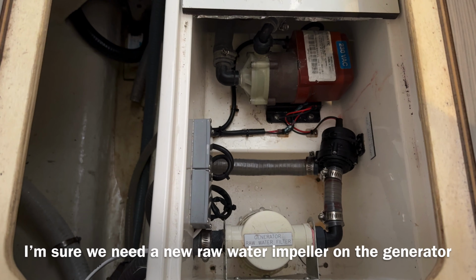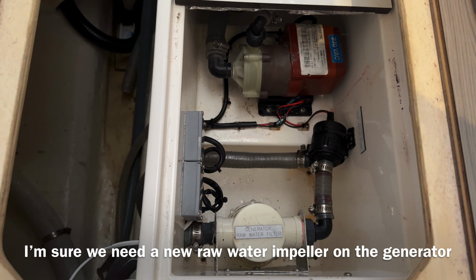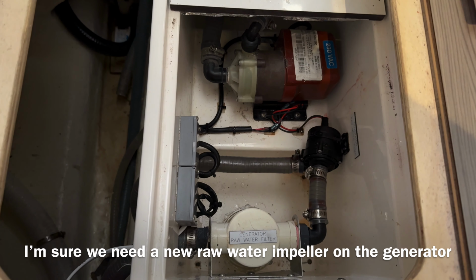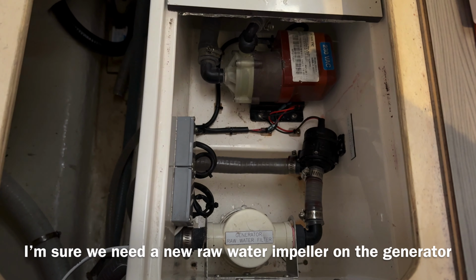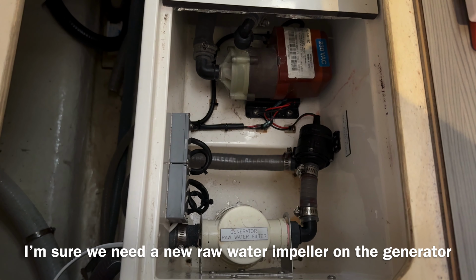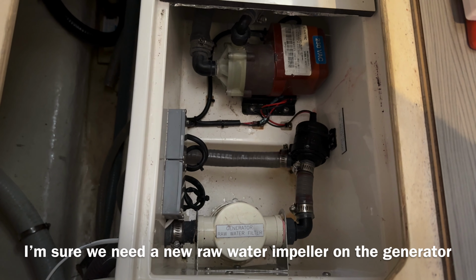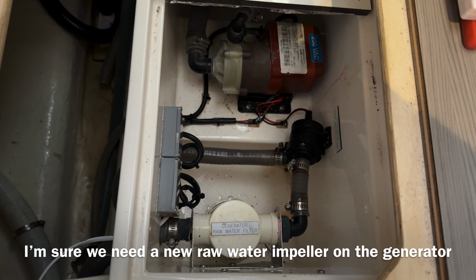We've cable tied everything back together. It did run for quite a long time, then had an overheat alarm. I'm fairly sure the raw water impeller on the generator engine needs to be replaced, because it will run dry a fair bit.